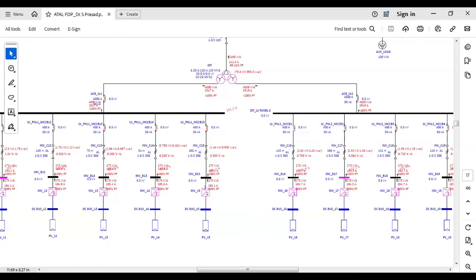The capacity of each inverter is 275 kVA, and this is the PV panel and this is the DC bus. The PV panel is connected to the DC bus, and the inverter is connected to the DC bus, because the inverter converts the DC into AC. Then it is connected to the AC bus, which is called the inverter bus. The inverter bus is connected through a cable to the LT panel of the IDT transformer. So these are the two LT terminal buses, 0.8 kV buses.